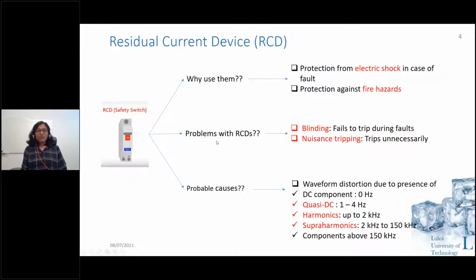So basically, what is this residual current device? A residual current device is used in low voltage networks for protection of people from electric shock. When there is a fault, and if it's an earth fault, the current doesn't return through the neutral and it would return through the protective earth. If you are by chance touching the live conductor, you will feel the shock. An RCD should be able to detect that and should be able to trip the circuit. So it is used for protecting people from electric shock.